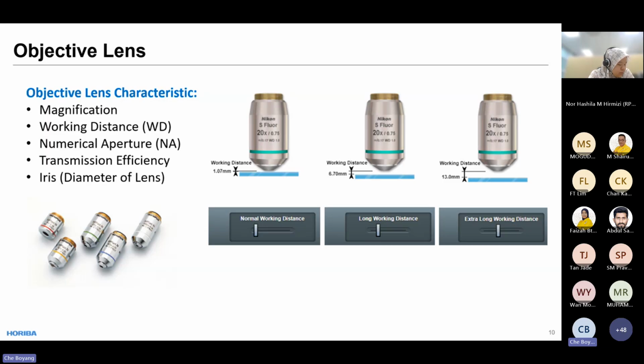Then you will need to be careful when you operate the instrument because you don't want your sample to touch the objective lens. It may cause contamination on the objective lens, and it may also damage your sample. In some cases, we can supply so-called long working distance objective lenses so that you will have a longer distance between your objective lens and your sample surface.